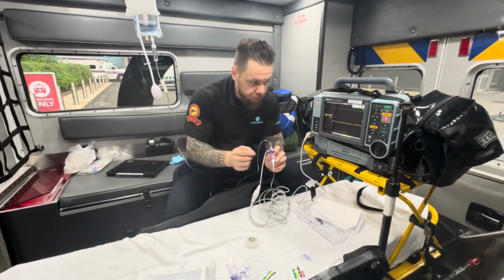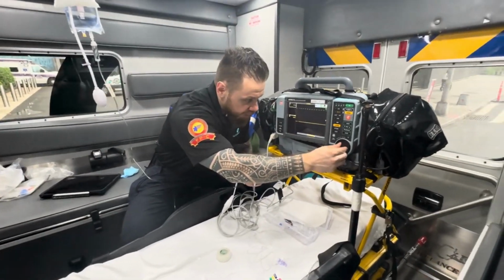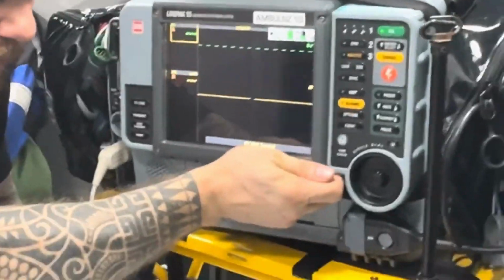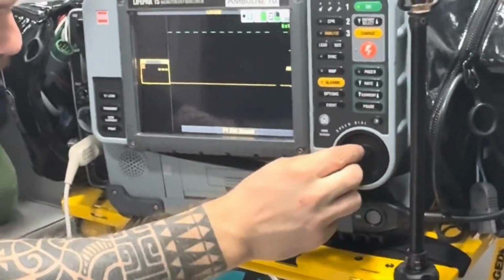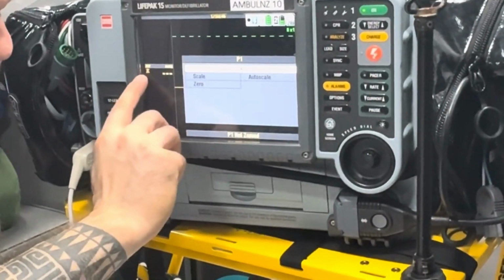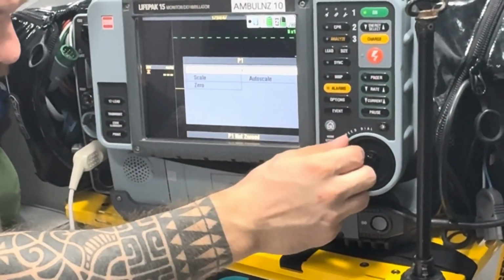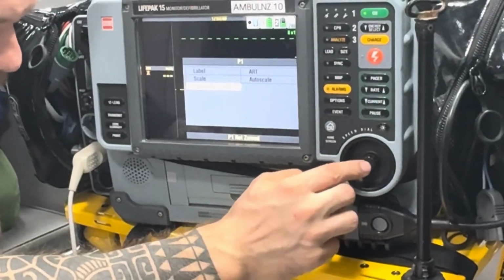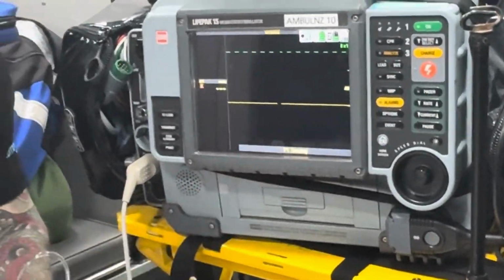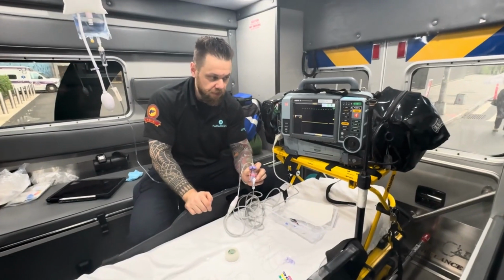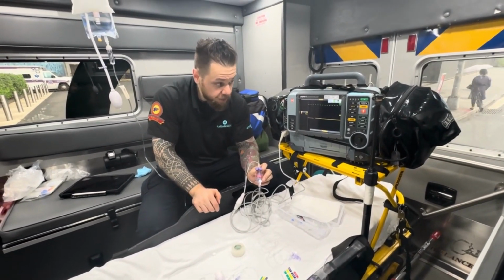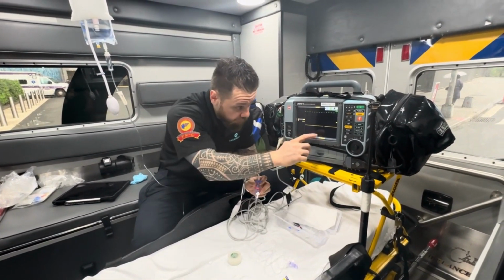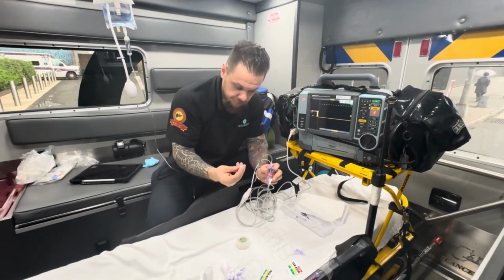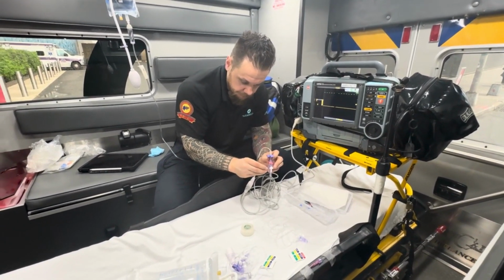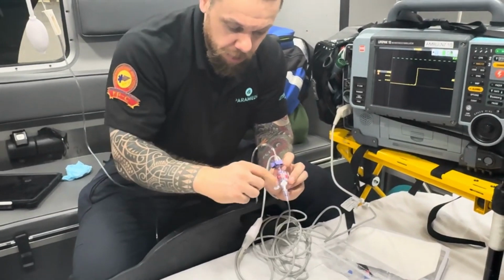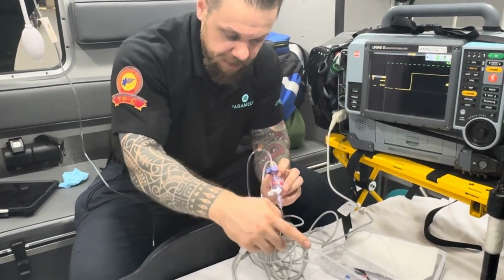What you're going to do now is move your dial. You're able to see the monitor, right? You're going to go in here on the P1 or arterial label, and you're going to say 0. You scroll down and click 0. It says P1 0. It will automatically zero the system. You don't have to do anything, you just have to wait. So we're waiting, it says P1 0. You're then going to replace your cap. Once I replace the cap, I close it off to the cap. So now I have connection to my patient.